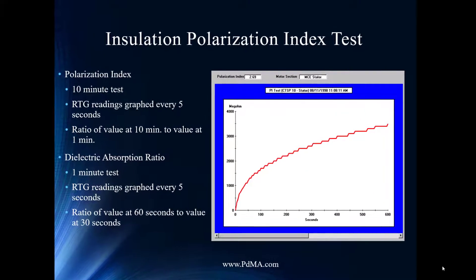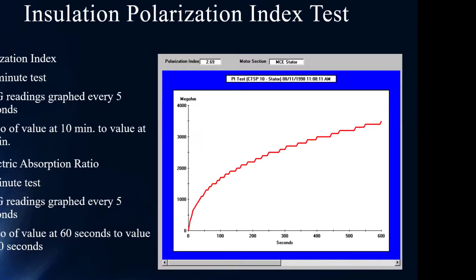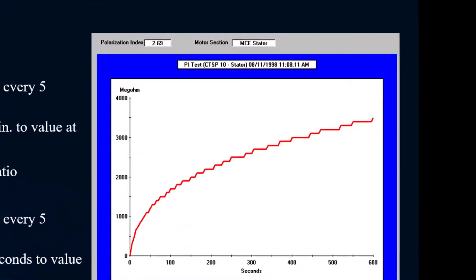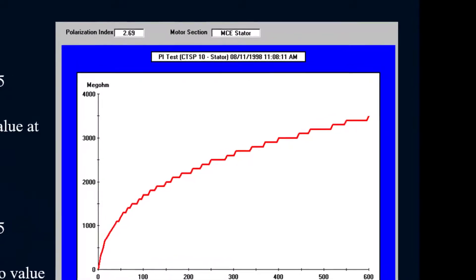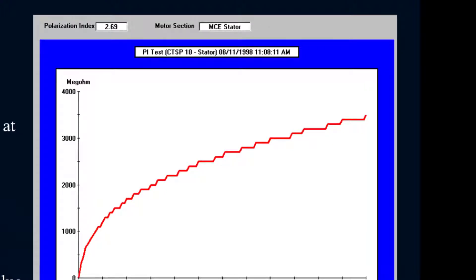We also perform a Polarization Index (PI) test — a 10-minute test where we hold a voltage (1,000V up to 5,000V), take a measurement every second, and display it every five seconds. Rather than just giving a quantitative resistance value, it provides a profile over time showing what the insulation is doing under charge. A healthy PI shows a gradual rise in resistance over time as the insulation molecules polarize under the DC charge. IEEE recommends a PI value of 2 to 5.